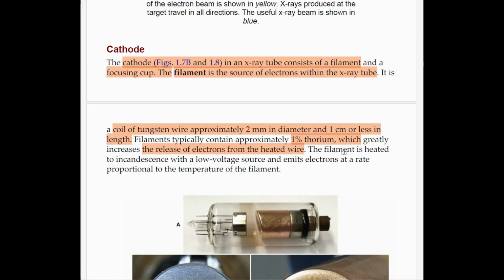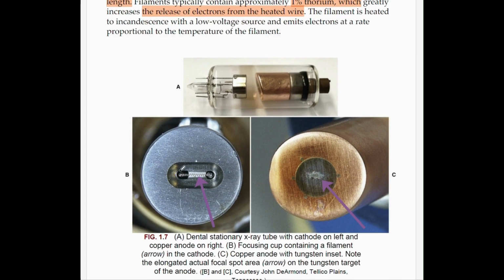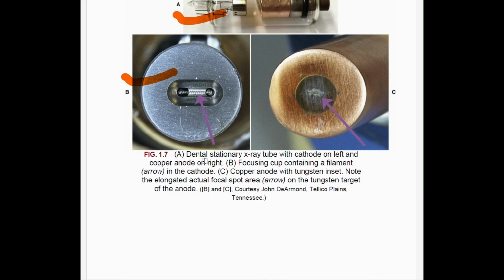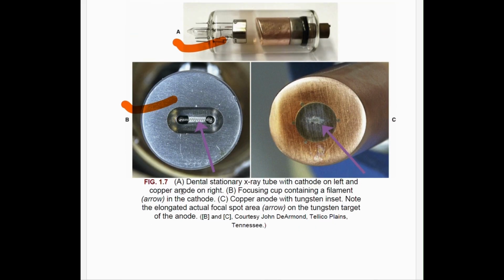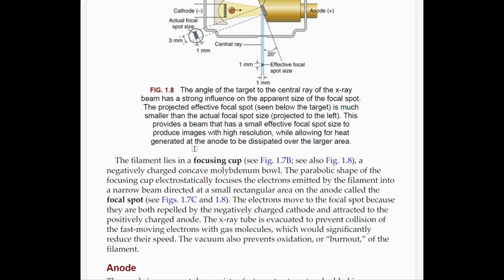Next important point that you need to mention. If you want, you can draw these diagrams. It shows the dental stationary X-ray tube with the cathode on the left and the copper anode on the right. This is the cathode, and the anode is made up of copper. Now we move on to the filament. The filament lies in a focusing cup, a negatively charged concave molybdenum bowl.